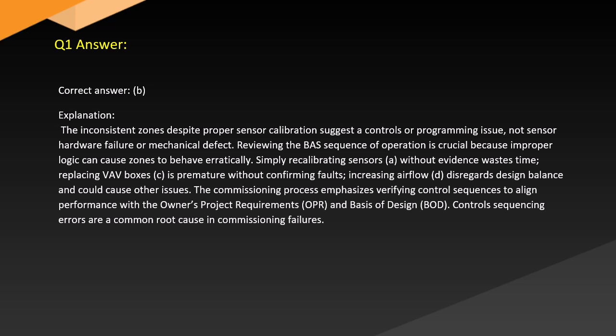Simply recalibrating sensors (A) without evidence wastes time. Replacing VAV boxes (C) is premature without confirming faults. Increasing airflow disregards design balance and could cause other issues. The commissioning process emphasizes verifying control sequences to align performance with the owner's project requirements, OPR, and basis of design, BOD. Control sequencing errors are a common root cause in commissioning failures.